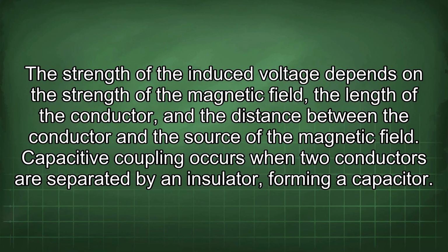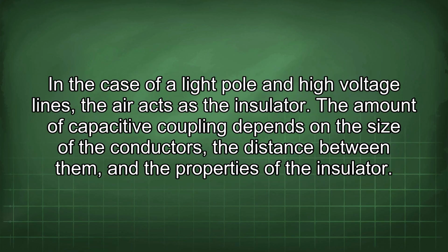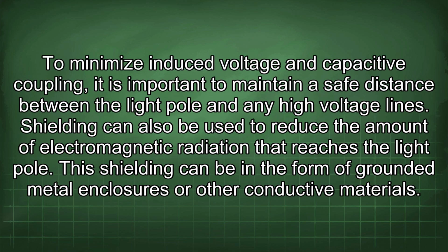Capacitive coupling occurs when two conductors are separated by an insulator, forming a capacitor. In the case of a light pole and high voltage lines, the air acts as the insulator. The amount of capacitive coupling depends on the size of the conductors, the distance between them, and the properties of the insulator. To minimize induced voltage and capacitive coupling, it is important to maintain a safe distance between the light pole and any high voltage lines.